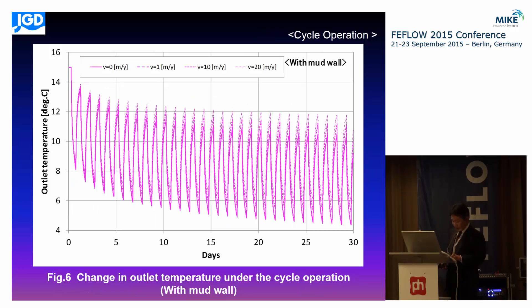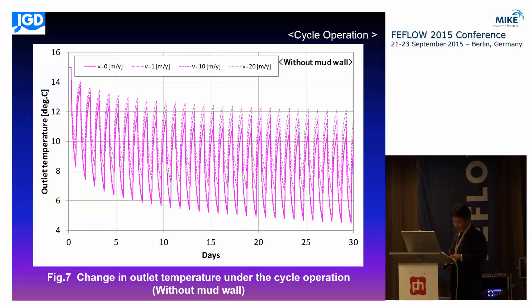Figure 6 shows cycle operation with mud wall. Regarding the daily operation, Figure 6 shows that regardless of mud wall existence, outlet temperature decreased every day as time elapsed. The difference in temperature drop of the outlet water was shown according to the groundwater flow velocity. On the other hand, the case without mud wall is shown in Figure 7. The changing trend is similar to the case with mud wall, but in this case, when the groundwater flow velocity is faster, the temperature drop is smaller and temperature recovery becomes more rapid.